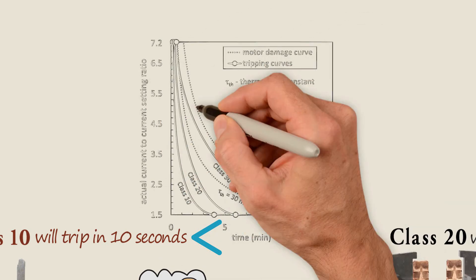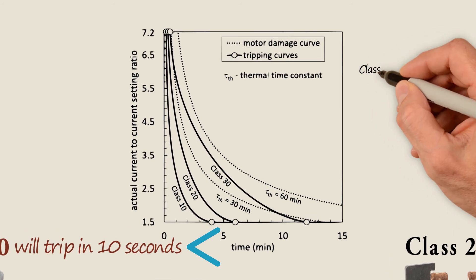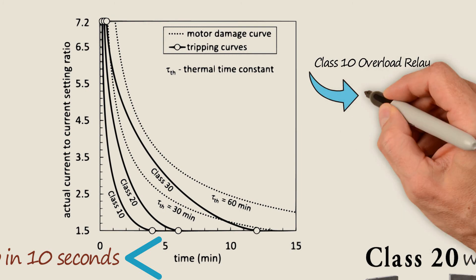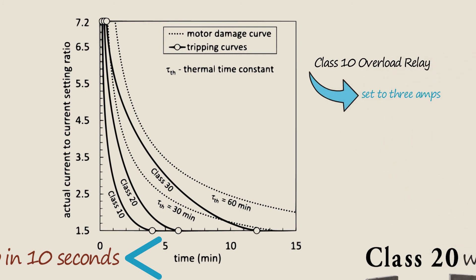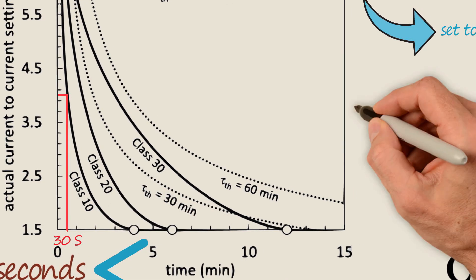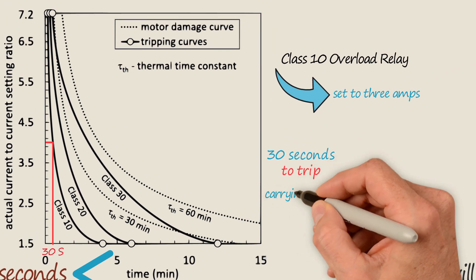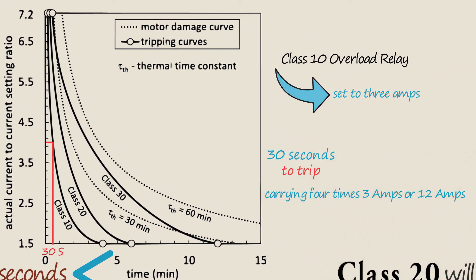Manufacturers should supply a graph that shows the tripping time as a function of current. As an example, consider an adjustable Class 10 overload relay that has been set to 3 amps. The graph shows it would take around 30 seconds to trip if it was carrying four times the 3 amps, or 12 amps.